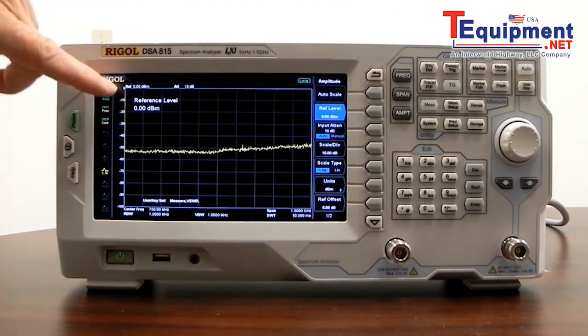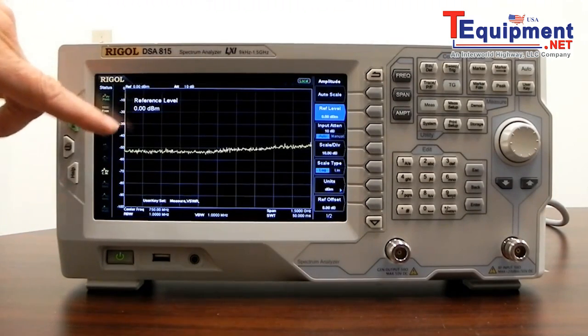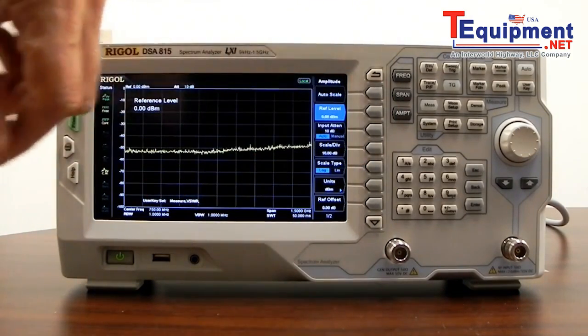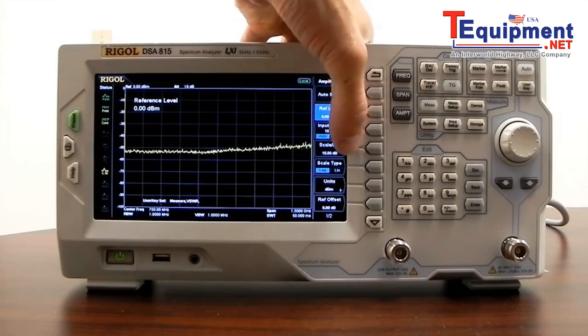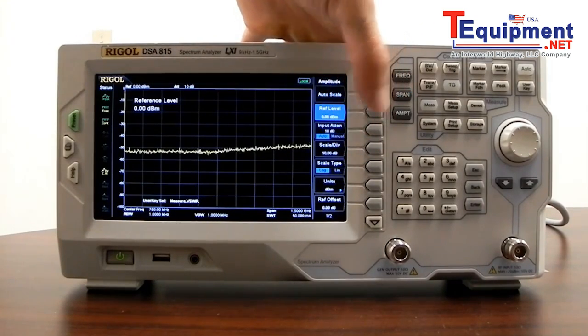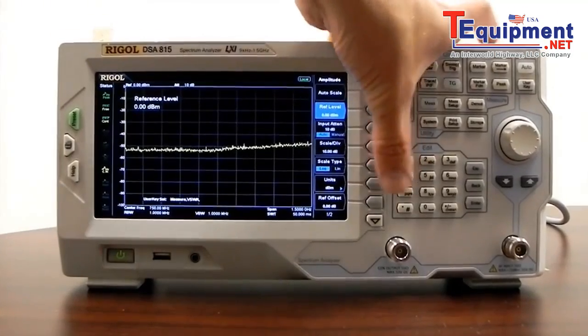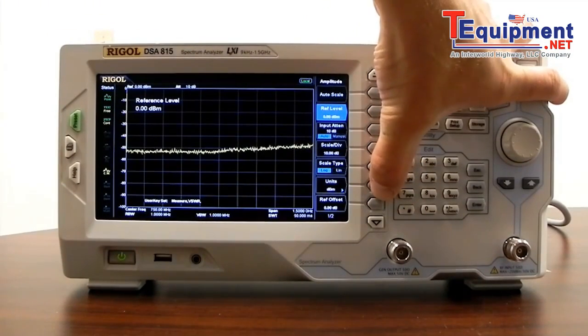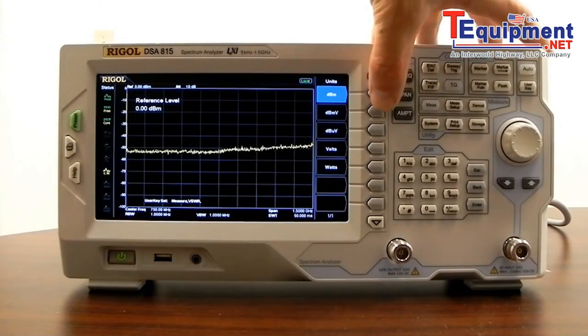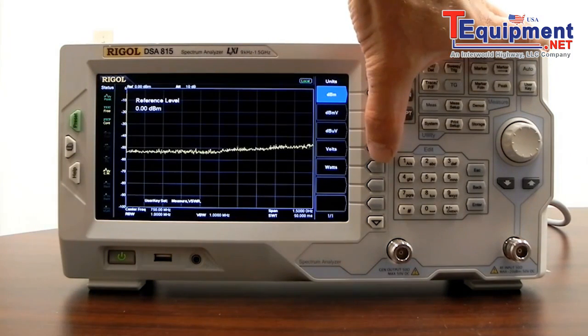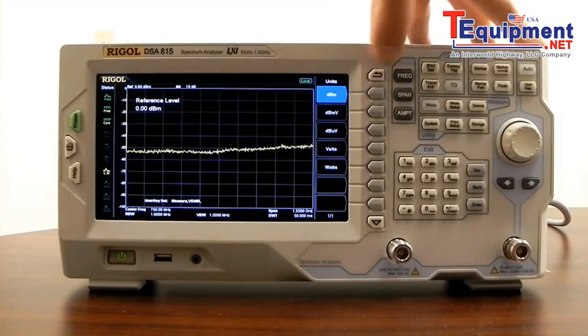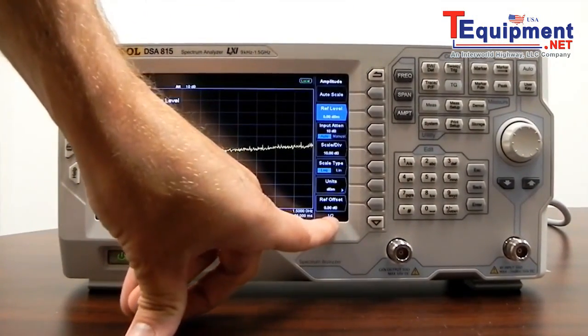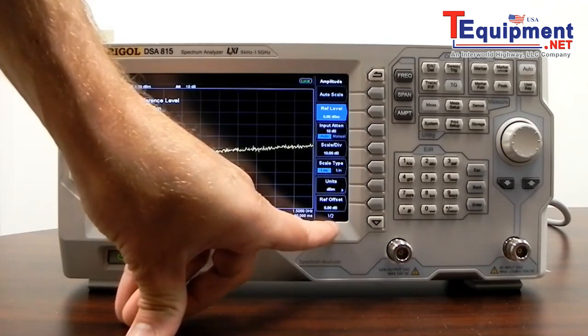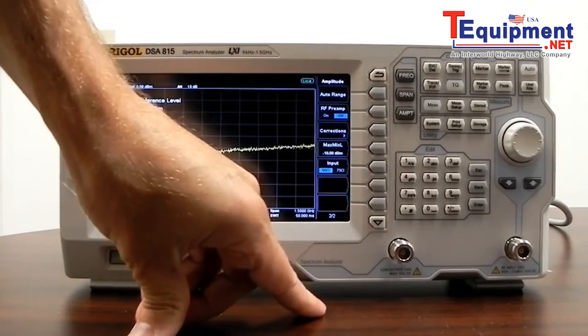Scale per division, again, we have 10 dB per division in this particular case, but we can change that very easily. You can also change that amplitude scale from log to linear. And units, this is an area that we get a number of questions about. You can set the units to dBm, dBmV, dB microvolts, dB volts, and volts and watts. We can also set a reference offset. You'll note down here it says 1/2. That means we're on menu page 1 of 2, so we can down arrow to get to the second page.